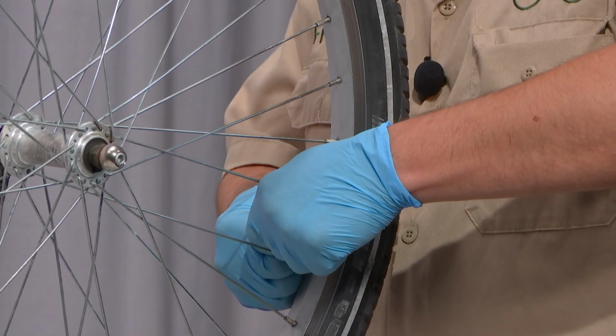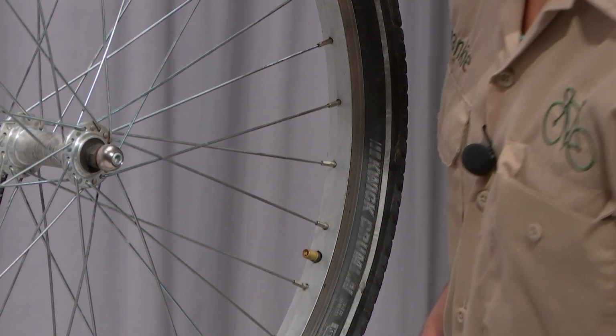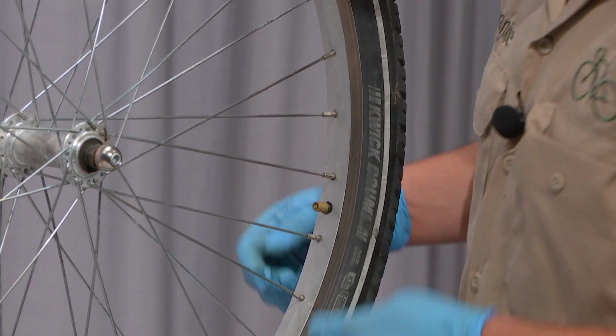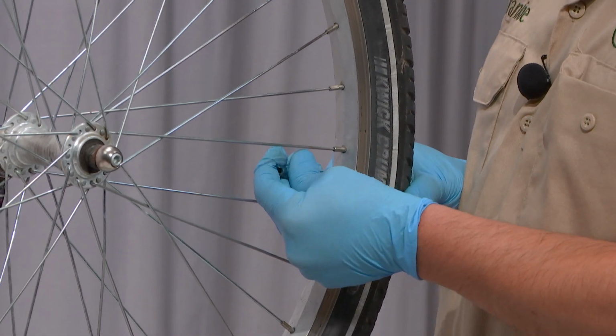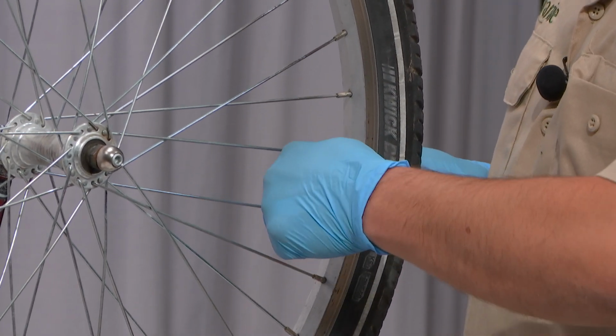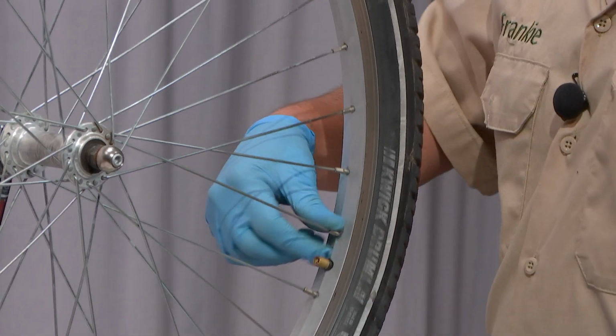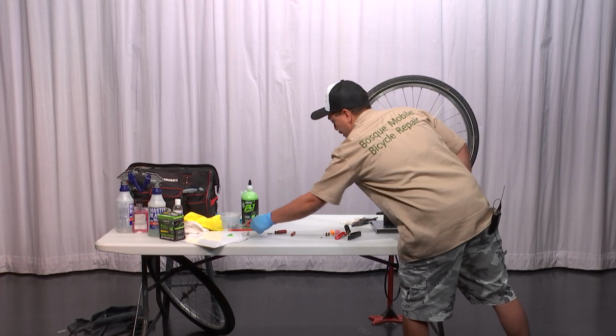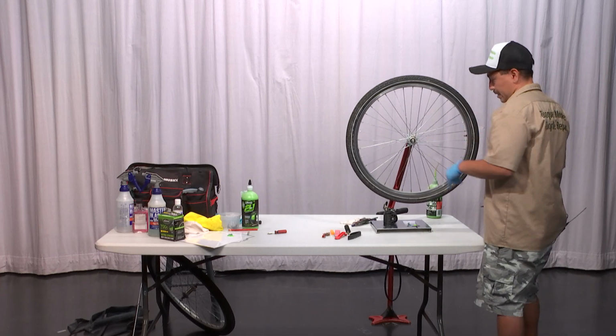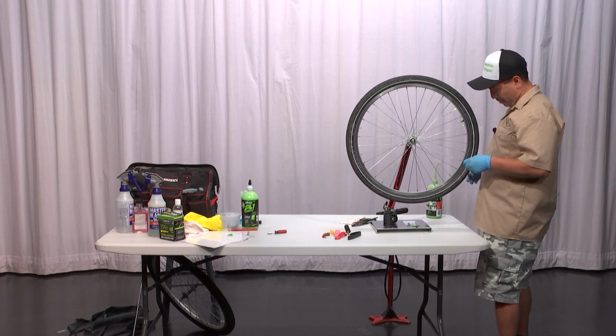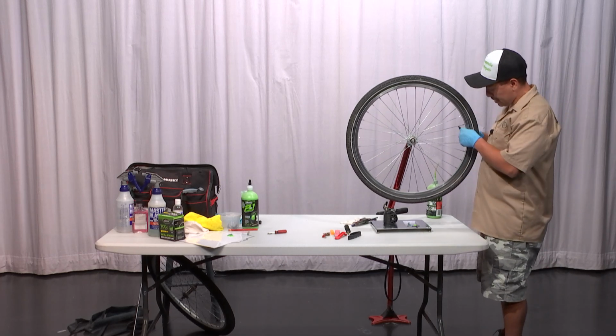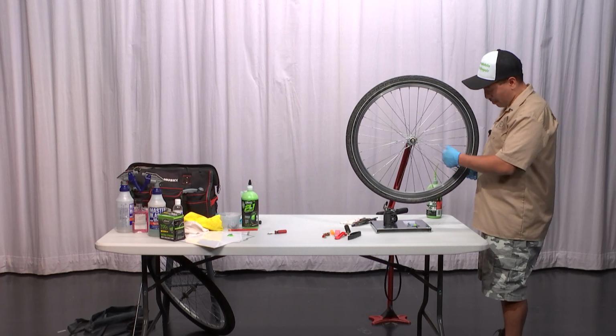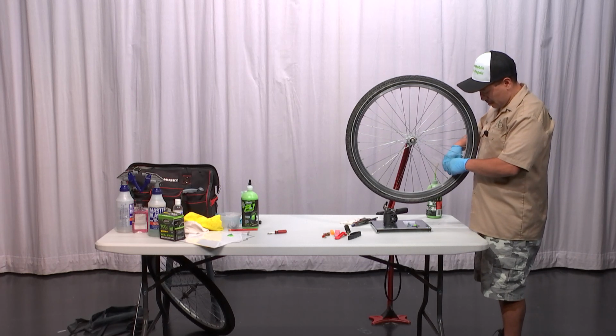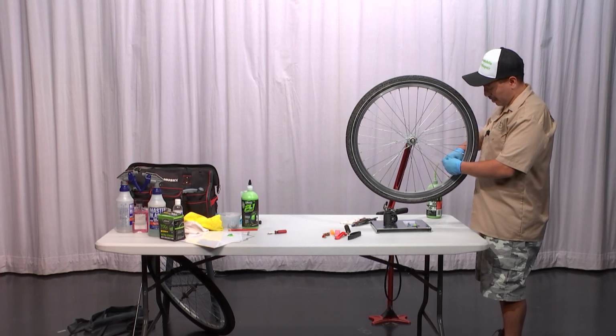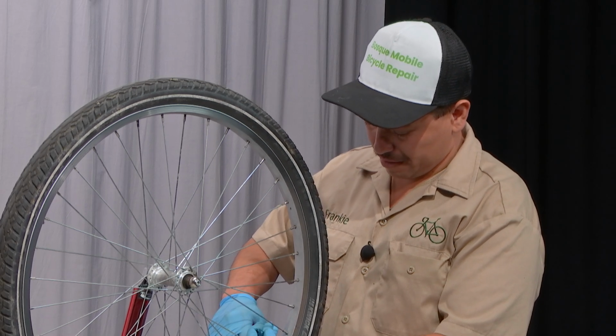Yeah, that valve core is in there tight. If it's that tight, what I do is get a pair of pliers to hold that valve. That's why I don't like using the plastic cap Schrader valve core removal tool, because if it's that tight and you use it, it's going to break off that piece of plastic, and you probably won't be able to get it out.